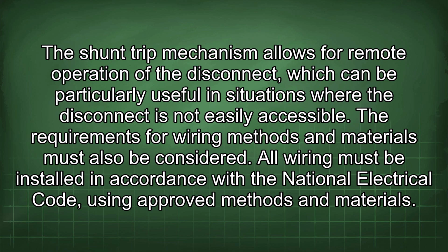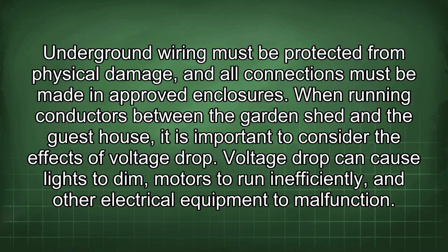The requirements for wiring methods and materials must also be considered. All wiring must be installed in accordance with the National Electrical Code, using approved methods and materials. Underground wiring must be protected from physical damage, and all connections must be made in approved enclosures.